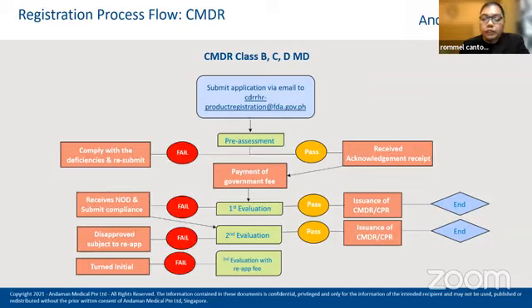But if there are deficiencies, FDA will issue an NOD and you must submit compliances via fdoc.pacd@fda.gov.ph. If the evaluator is not satisfied with the compliance submitted and needs more clarifications or documents, then a second evaluation will take place. If you pass the second evaluation, then you will receive the approved CMDR. But if you fail again, you will receive a disapproval letter. But the good thing here is that you can reapply within 60 days upon receipt of this disapproval letter.